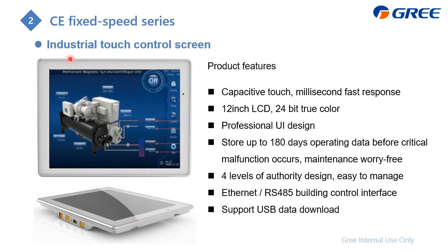This is the controller of the CE series. It is a 12-inch touch screen, and it can store up to 180 days of operating data before a malfunction occurs. You can also download it to a USB and analyze it on your computer. We also support connecting with an Ethernet cable, which is here, for the BMS. There are 4 levels of authority design, which makes management easier, and you can allow service people or maintenance staff different authority.